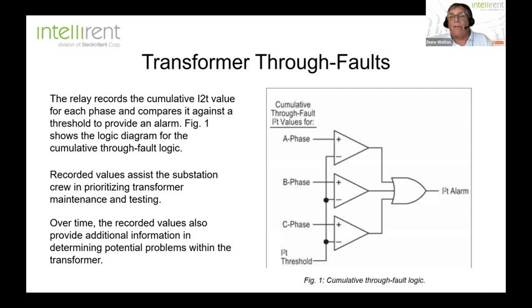So, how do we know when a through fault has happened? Well, I talked to my friends in the relaying groups, and one of them from Schweitzer Engineering, who I'm close friends with and who specializes in transformer protection, says, Drew, most of your protective relays on a transformer, your digitals, have through fault monitors on them, where they look at the through fault occurrences and capture the magnitude, the date and time when it happened, and how long the fault was there. He said, as far as he knew, he thought maybe about 80% of those that set the relays never enable the through fault monitor. So how would you ever know that you had a through fault unless you incorporate the through fault monitor, which is just looking at these events, and if they're high enough or exceed the rating of the transformer, will simply alarm. This isn't an element that's going to trip your transformer offline because it may just be a quick transient, but it's very, very important.